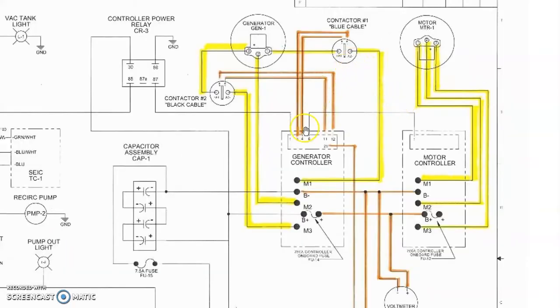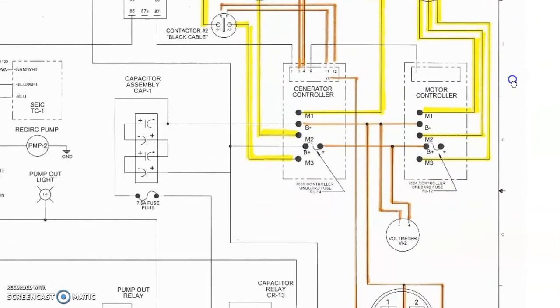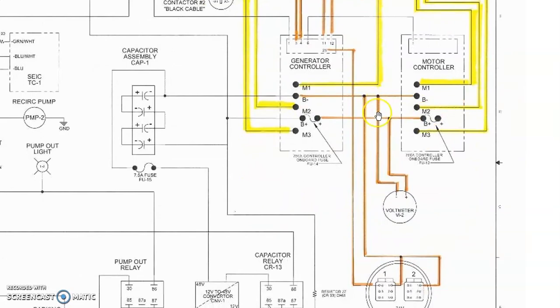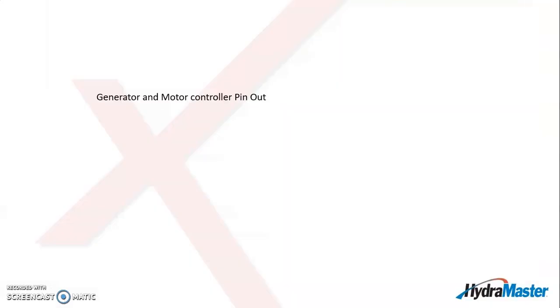You can see contactor number 1 is operated by pin 3 and pin 4, and solenoid 2 is pin 11 and pin 12. So then that comes to M1, M2, and M3, and off of the motor controller, M1, M2, M3 again, and again the 3 phases to drive the motor. You also see that this is the DC side, so B plus, or 48 volts positive, 48 volts negative. Also power for that meter in the front, and then the power for the tachometer. So those are the circuits.